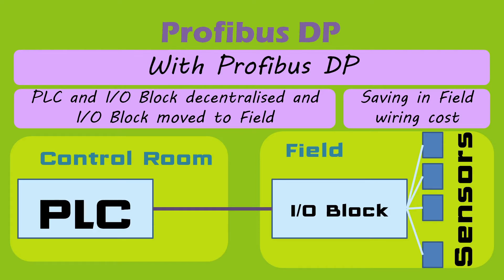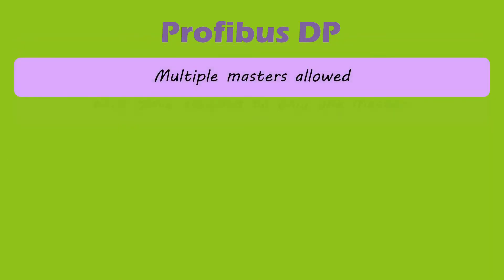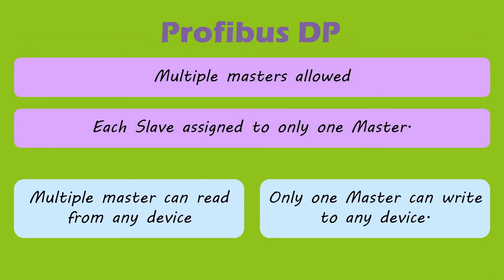Decentralization resulted in saving of wiring cost. Profibus DP allows use of multiple master devices in one network, in which each slave device is assigned to only one master. This means multiple masters can read inputs from any device, but only one master can write outputs to any device.